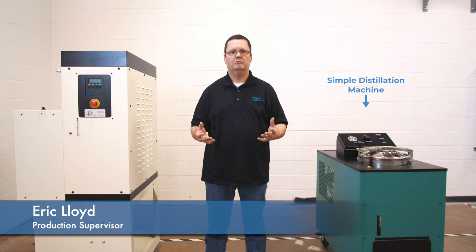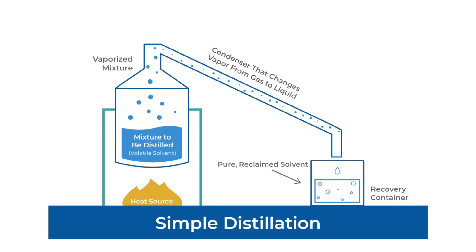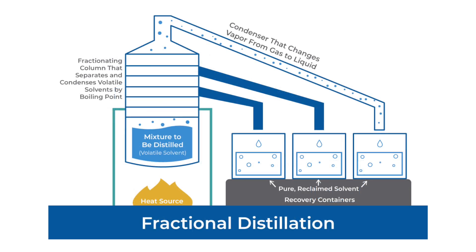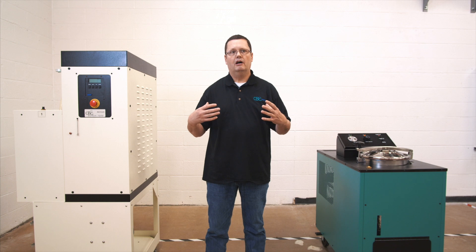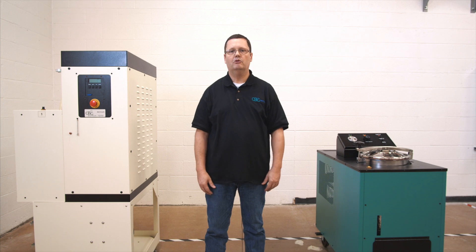If you're recovering the same product on a regular basis, the simple distillation machine is the product that you want to use. Simple distillation is to recover a single solvent into a recovered container to be used at another time. Fractional distillation is a process of separating various component parts into different fractions to be recovered. If you are recovering multiple products, you want to use a fractional machine because that's the machine that will recover multiple fractions for you.